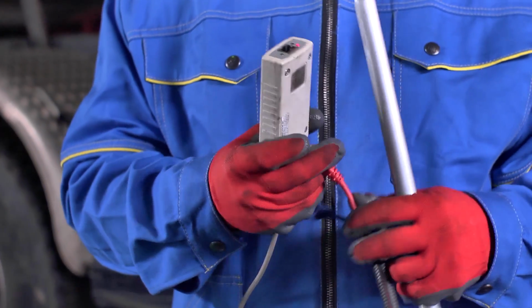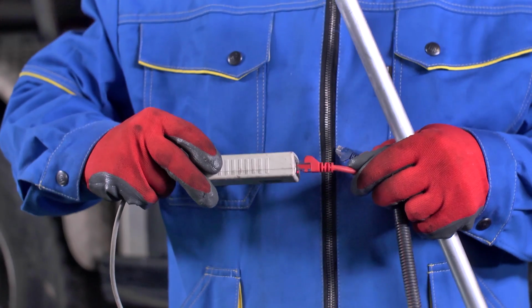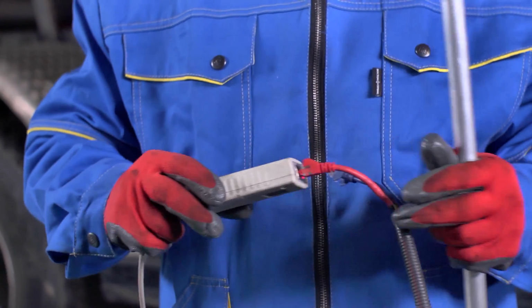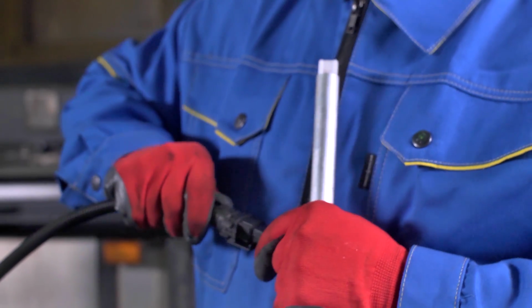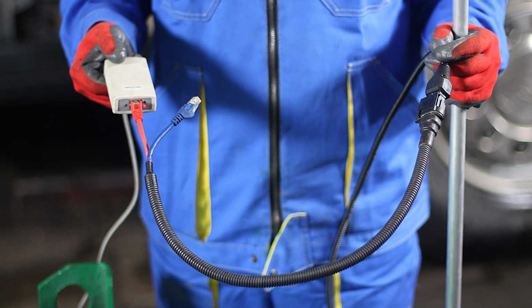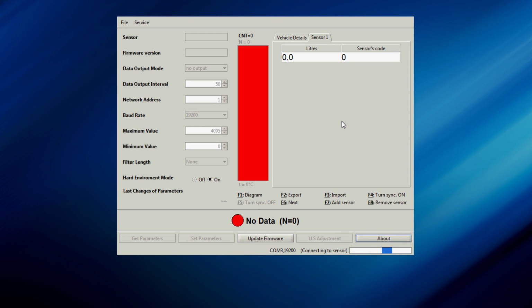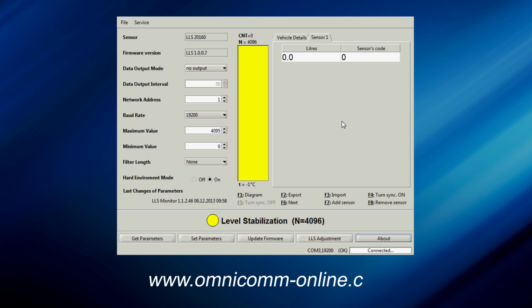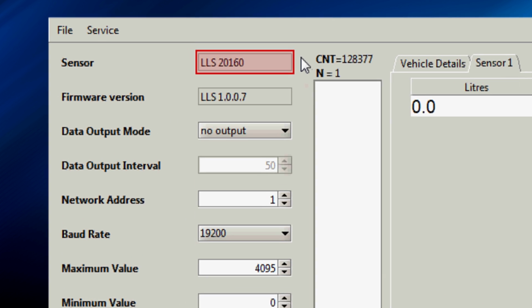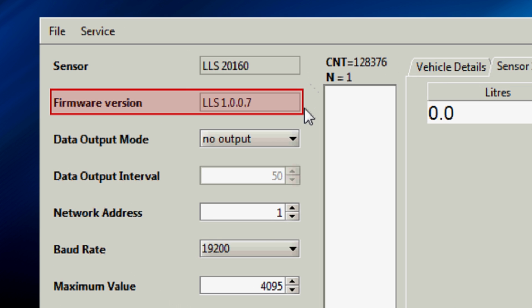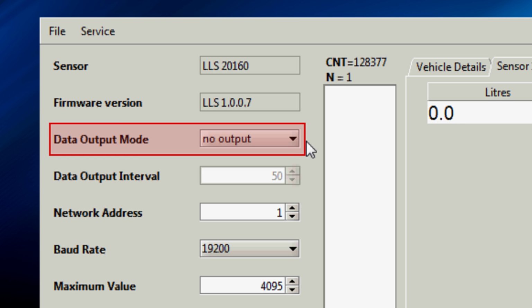Use the reusable tool UNU to connect the sensor to a computer and configure it. The UNU comes complete with the full set of connecting cables that you may need when installing Omnicomm equipment. Configure the sensor using the LLS Monitor application that can be downloaded free of charge from the www.omnicomm-online.com website. You can use this application to find out the type of your device and the version of its firmware. Enable the data output mode.